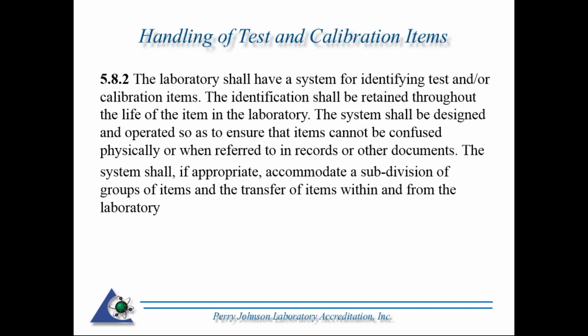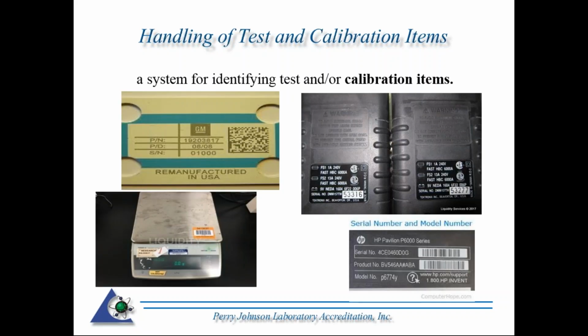Typically with this section as an assessor, I'm looking for some sort of traveler that's kept with, in my case, mostly calibration items that are sitting in the facility, perhaps waiting to be calibrated. So, a system of identifying test or calibration items. For calibration, I see an array of methods. Often it could be right on the artifact, i.e., serial number, make, model. Could be a permanent identification, uniquely identifying a particular item. Could be an internally generated item, such as an asset number or customer ID number.